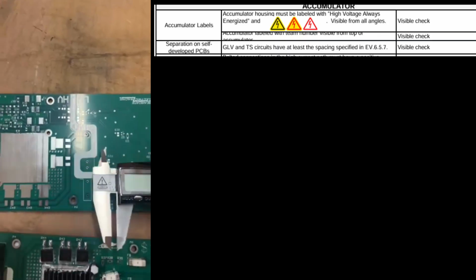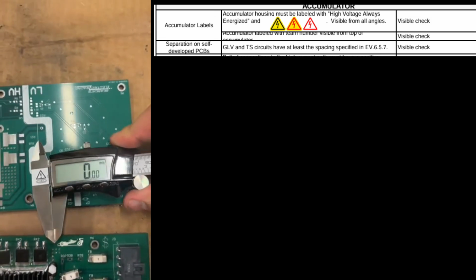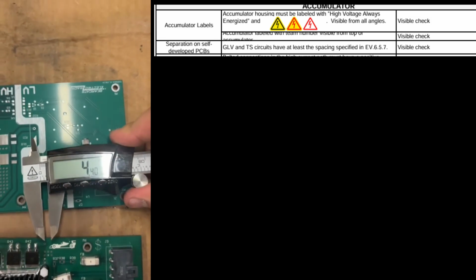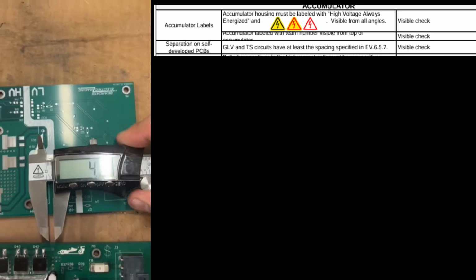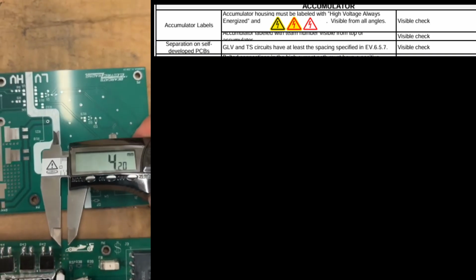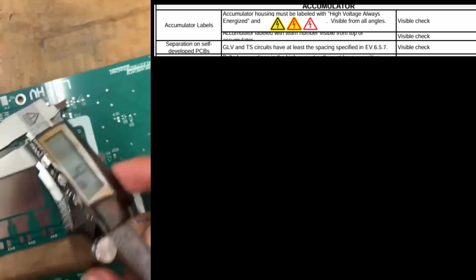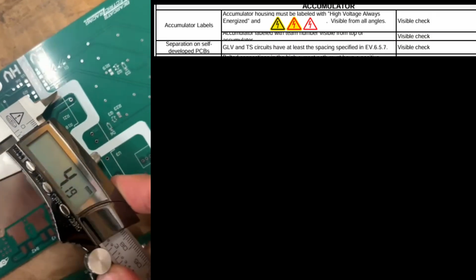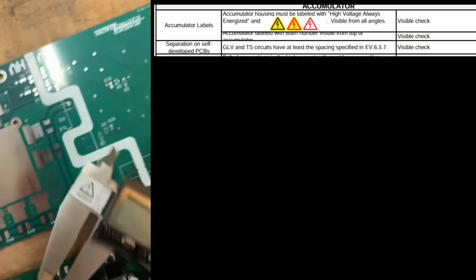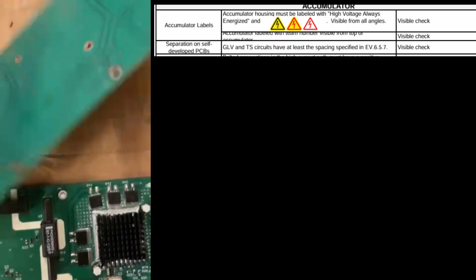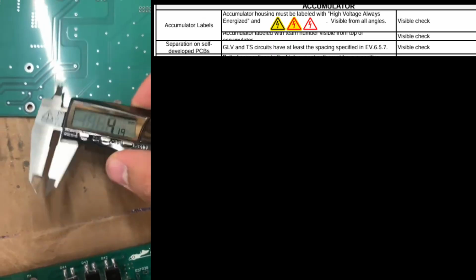On this other board, which is a copy of this one, I'll show you the spacing. I've got calipers zeroed and set to about 4 millimeters, which is the prescribed distance for boards with conformal coating at our voltage level of 357 volts. You can see that our separation, represented by this white line, is greater than that minimum, both on the front and the back side.